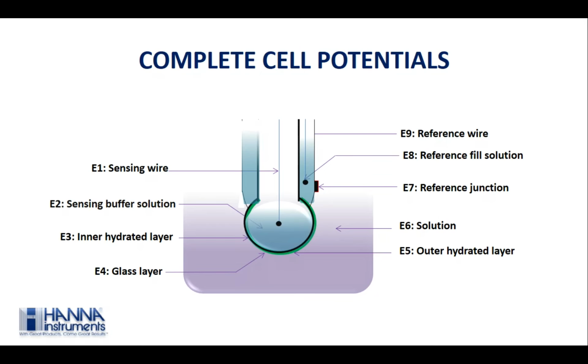So before going towards maintenance, first we will see the working of a pH electrode. As you can see on your screen, a pH electrode consists of a sensing bulb, a sensing wire, a sensing electrolyte, a reference electrolyte, and a reference ceramic junction. The sensing bulb, sensing wire, and sensing electrolyte are responsive to the hydrogen ion activity present in the solution and give out variable millivolts in response to the hydrogen ion activity, whereas the reference electrolyte is responsible for giving out a stable voltage. This reference electrode is in contact with the sample through the ceramic junction. The pores in the ceramic junction allow the reference electrolyte to flow out of the electrode at a steady speed.